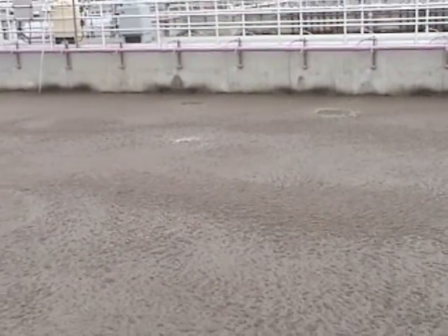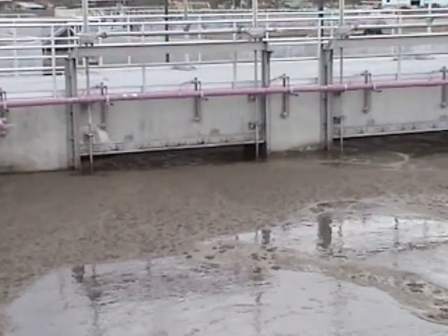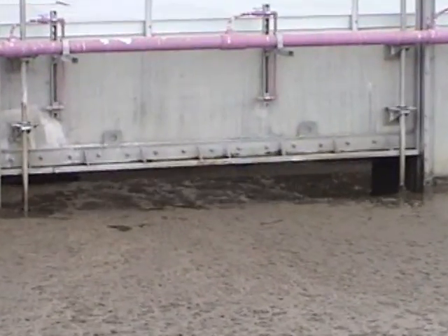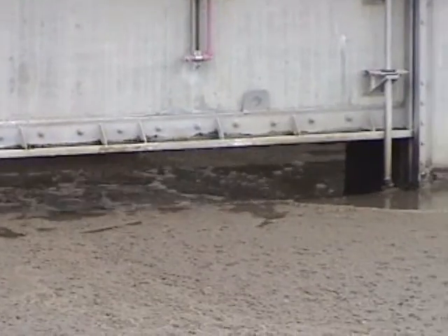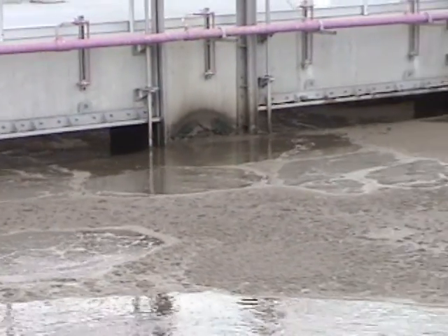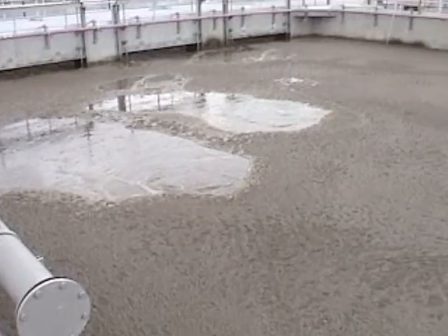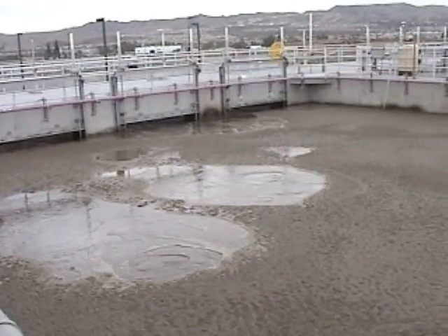I think what we're probably going to have to do is open and close some gates and let it flow into the secondary system. You can see it flowing over the weirs right there. What we're talking about doing is increasing the amount of flow through diversions to push it out to the secondary system. Nocardia is tough to deal with. At RP2, we used to vector it off and take it to the sludge drying beds and let it bake in the sun. You can use water sprays to get rid of it, but basically you're not getting rid of it. You're just helping it along to get out of the system. It's difficult to deal with. If it gets started, it's pretty bad, because if you don't deal with it right away, you can have a really big problem.